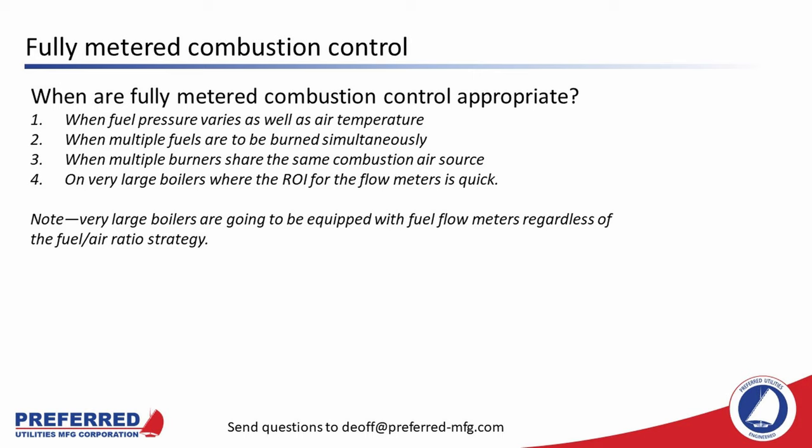Fully metered combustion control is really the only way to do simultaneous fuels safely, and we see it in larger boilers. When multiple burners share the same combustion air source, fully metered controls are usually required — this is how utility boilers are run. Utility boilers might have 36 burners but just one combustion air fan; the fuel is measured at one flow meter at the header and the air measured through the combustion air fan, then the fuel is split to however many of the 36 burners are running. Fully metered controls might also be appropriate on very large boilers where the ROI for the flow meters is quick. Note that very large boilers will have fuel flow meters regardless of the fuel-air ratio strategy, so sometimes there's no extra expense in doing fully metered controls versus parallel positioning with O2 trim.